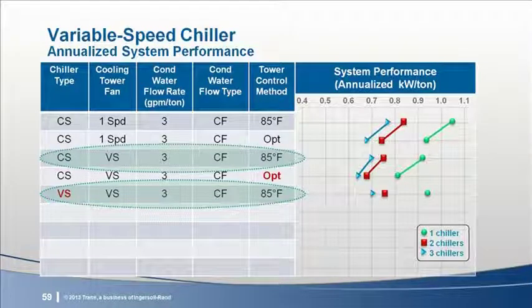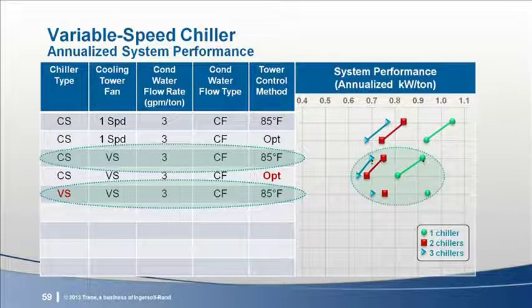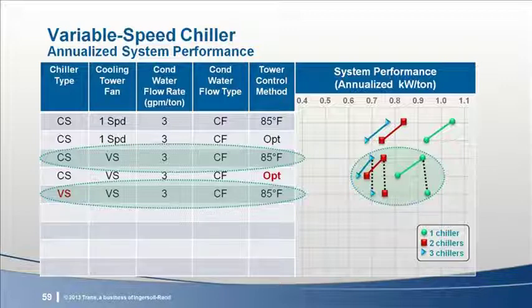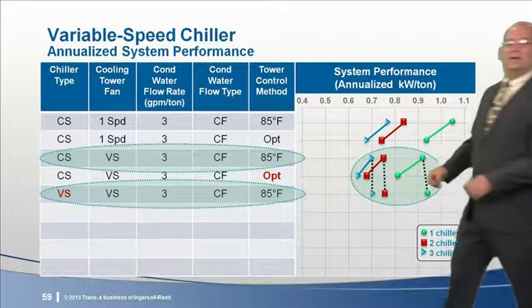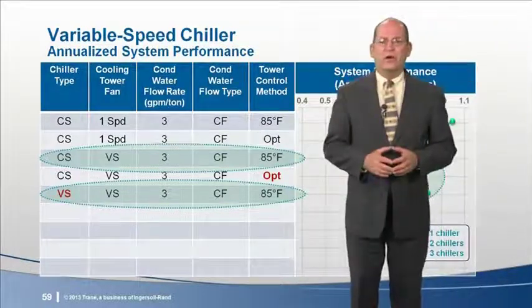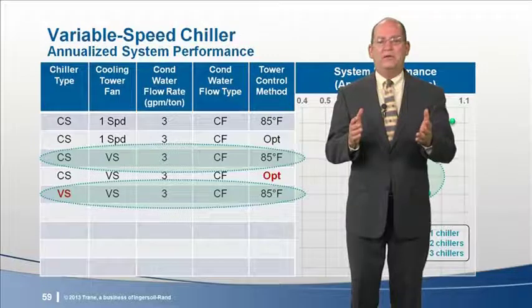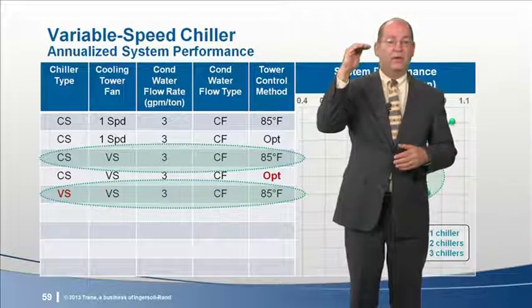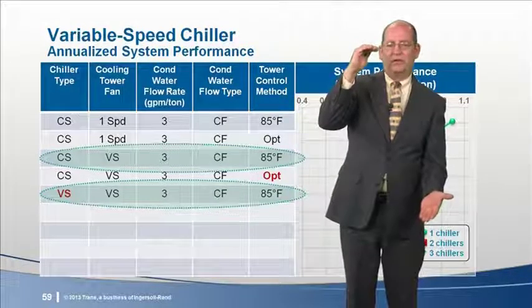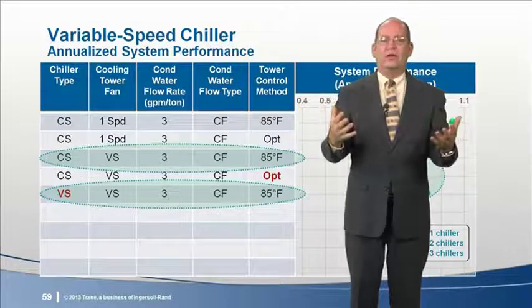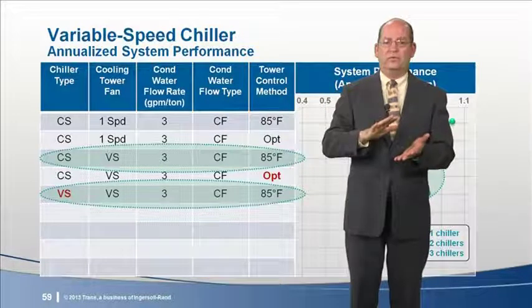Here's the performance. Worse than a similar system with a constant speed chiller. No matter how many chillers are operating, the performance is less efficient. This looks surprising, but it takes us back to the basics of a variable speed drive on a centrifugal compressor. The lift the compressor must overcome is proportional to the difference between the condenser leaving water temperature and the chilled water leaving temperature. In order for the drive to slow down, the compressor lift must be reduced.